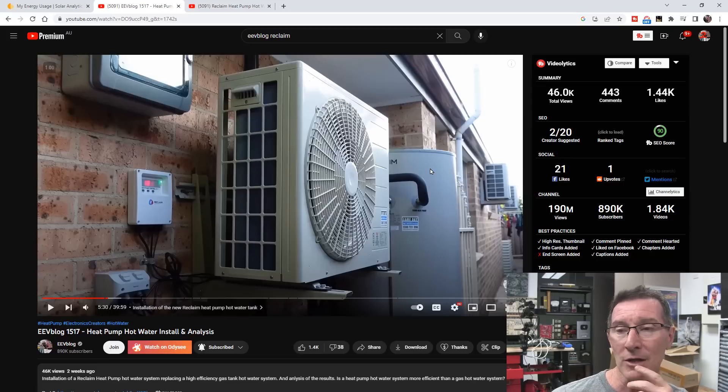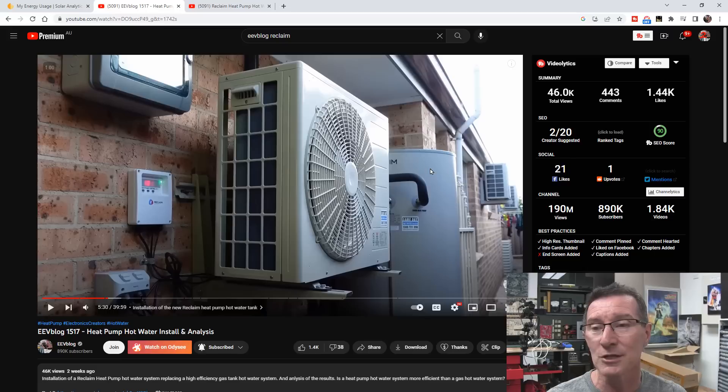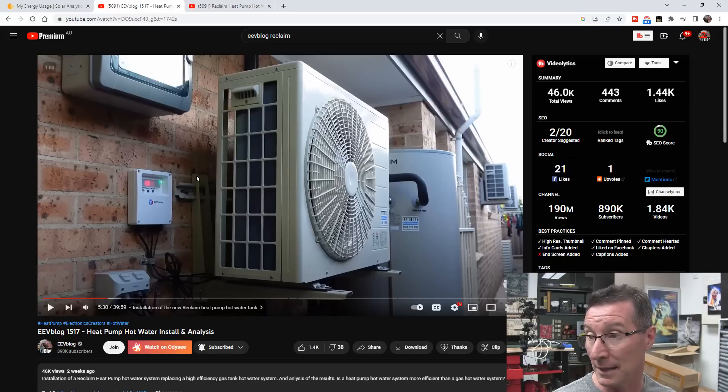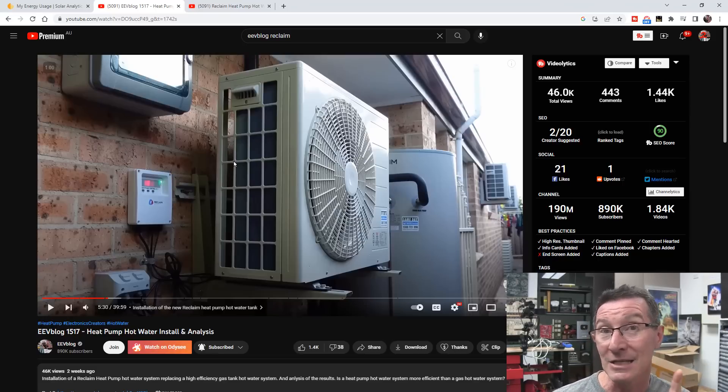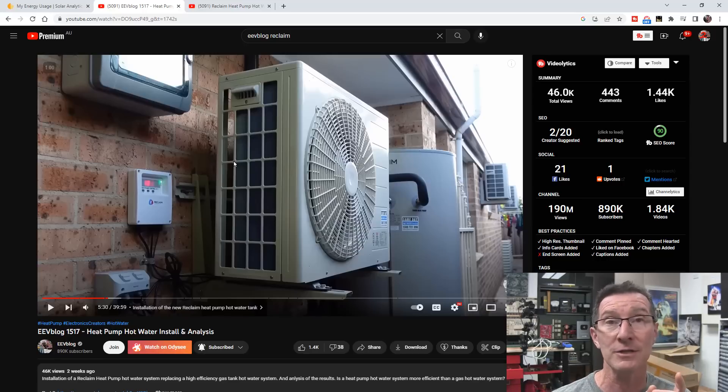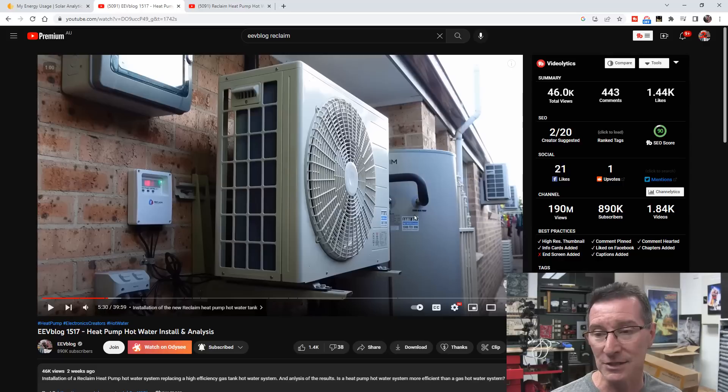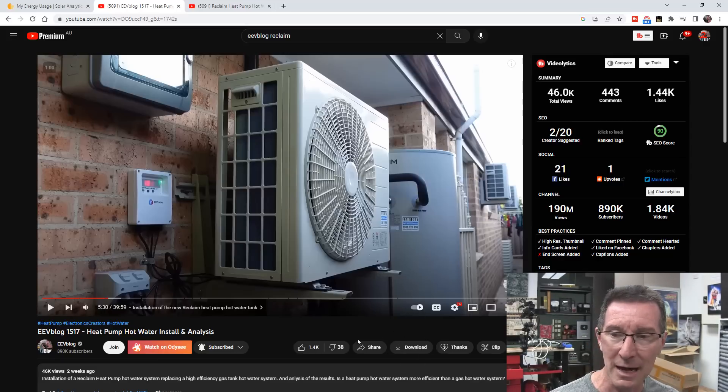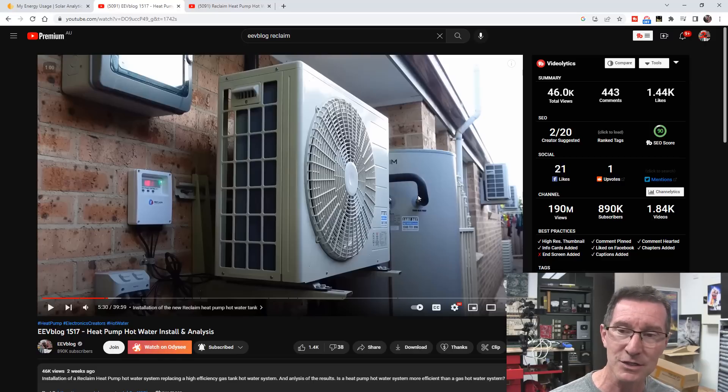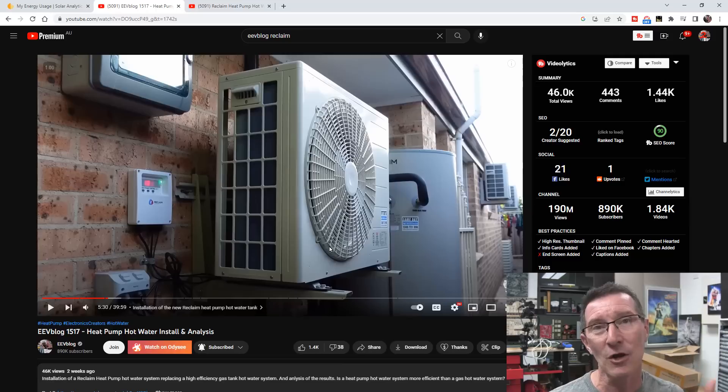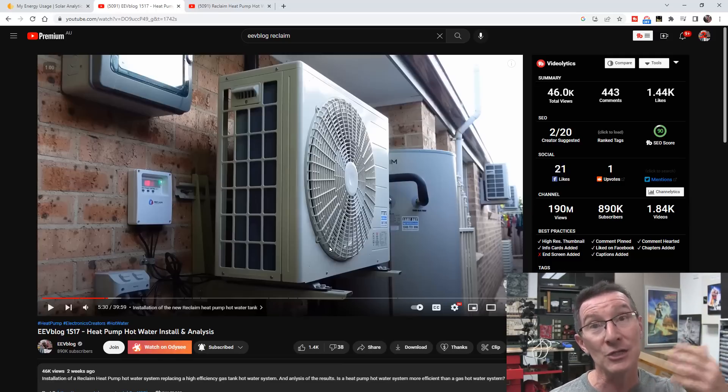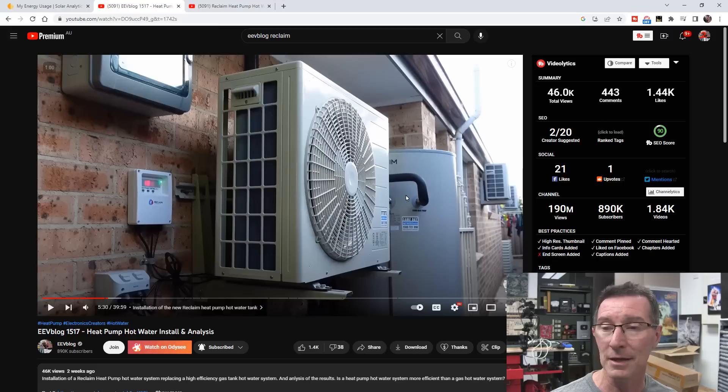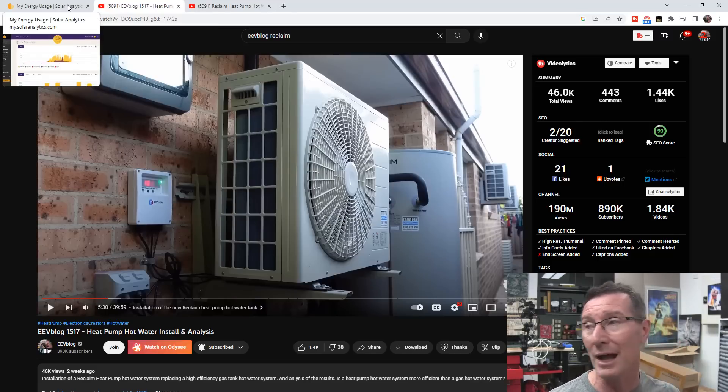Well, the first thing to realize is that this Reclaim unit, I'm not sure about other units, but this one specifically has a mode in the controller that will ensure that the tank at least once every day reaches 58 degrees Celsius. That's the sensor down the bottom, the bottom third. It pumps out 63 degree hot water at the top, 58 degrees down the bottom, but it actually operates at least once per day. That's to prevent legionella build-up in the water. So yes, it is actually going to turn on when we're not there.